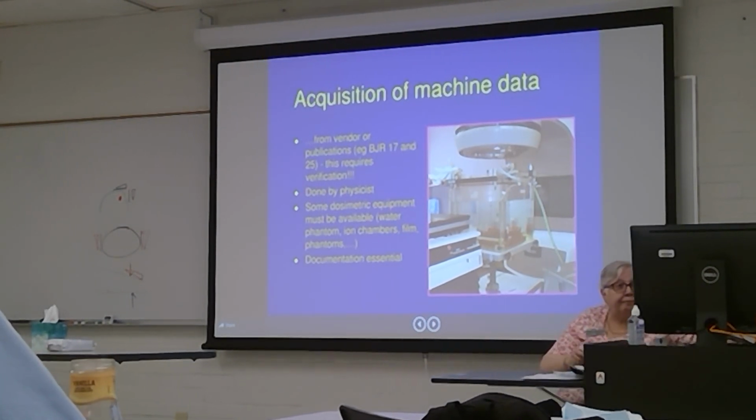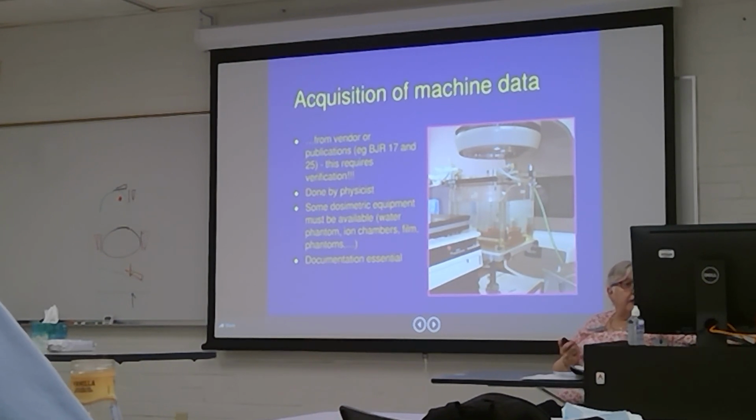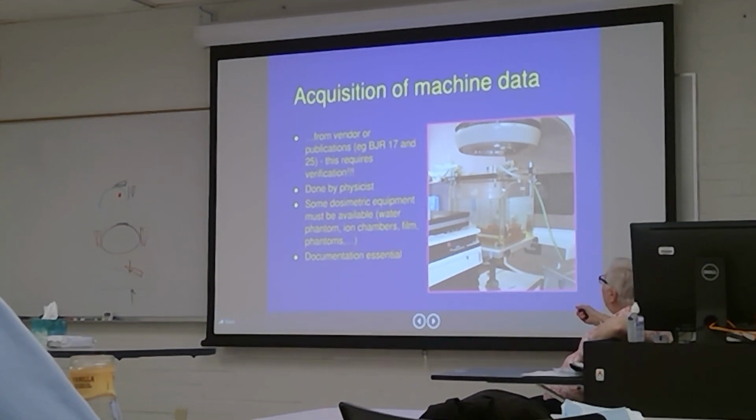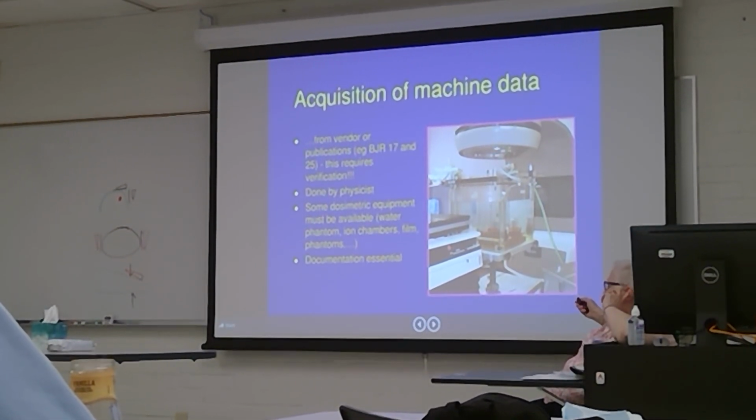Acquisition of beam data. We'll do this later on this semester, towards the end. So has anybody ever seen one of these? The older version of it. I've seen it, but I haven't seen him use it. You know what it's called? Water bath. Yes, water bath. And normally you would see the physicists wandering around with it. It's usually empty to get it into the treatment machine.